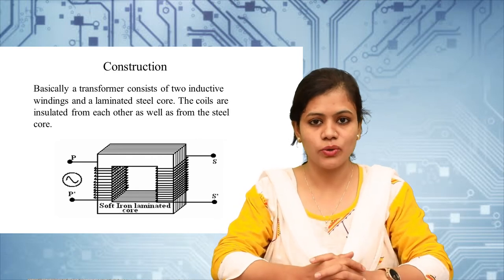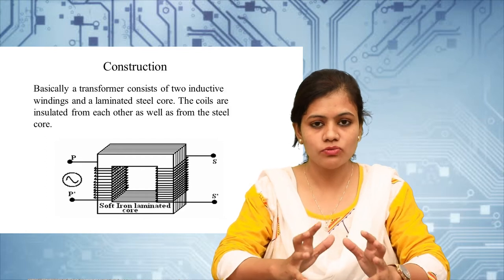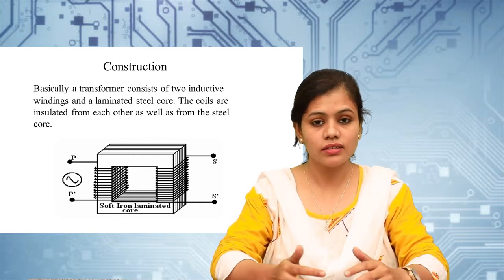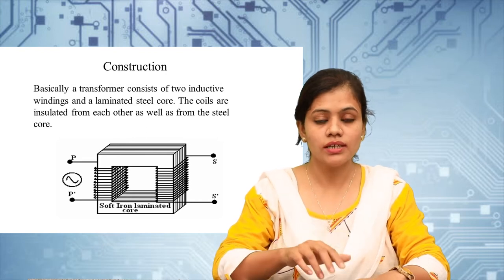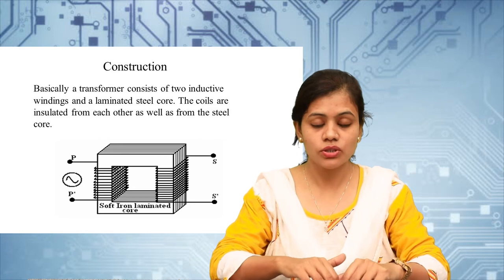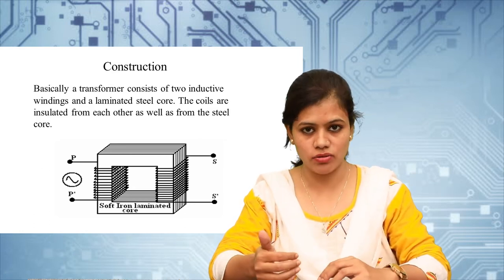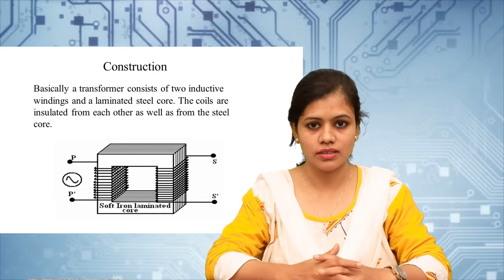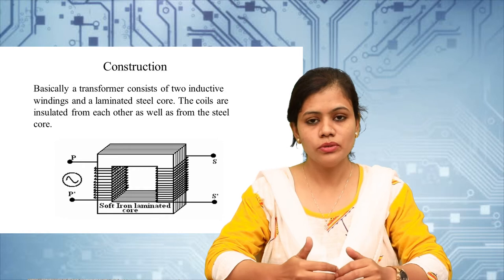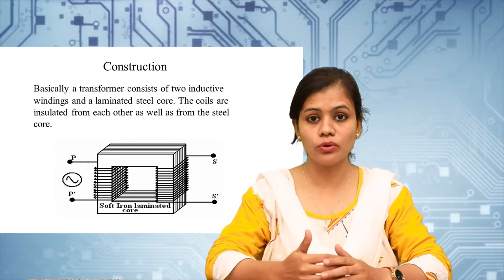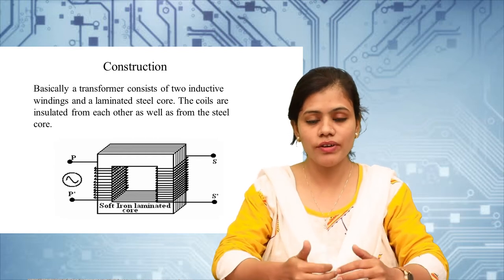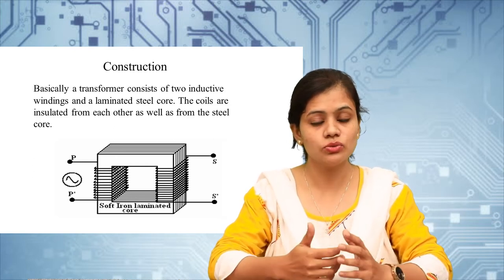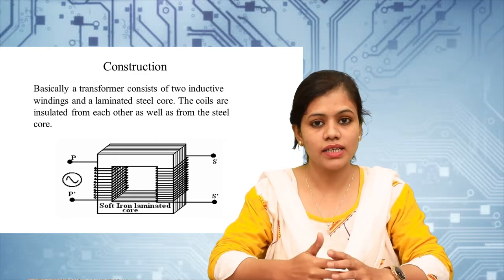Next is the magnetic core. The magnetic core in a transformer looks like a rectangle as shown in the figure. The main function of the core is to provide a path for the passing flux. When the maximum flux passes through this core, two types of losses occur inside the core — hysteresis losses and eddy current losses. To minimize these losses, the core is made up of high-grade silicon steel, because this material has high permeability.